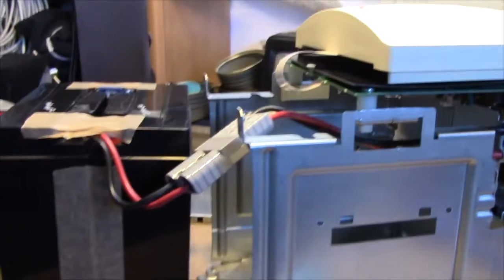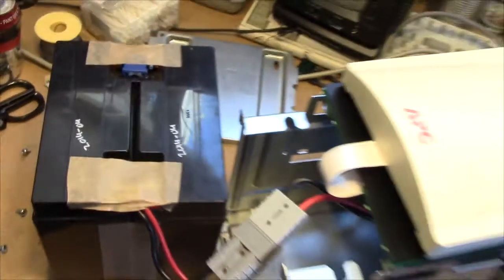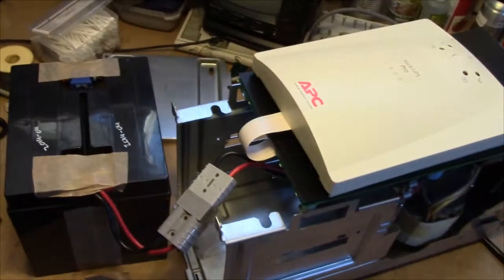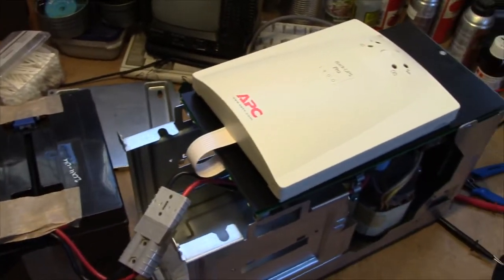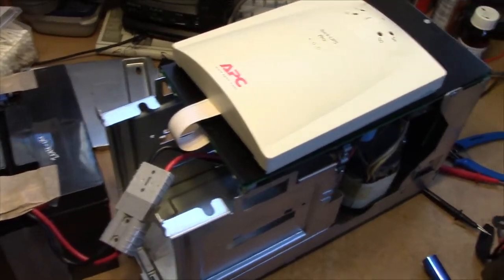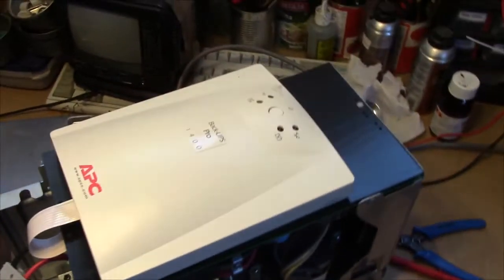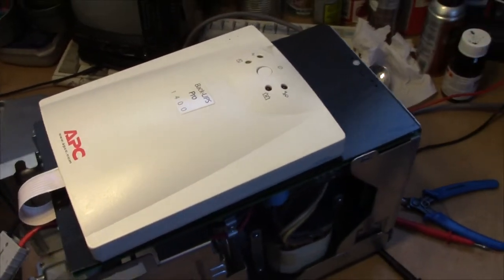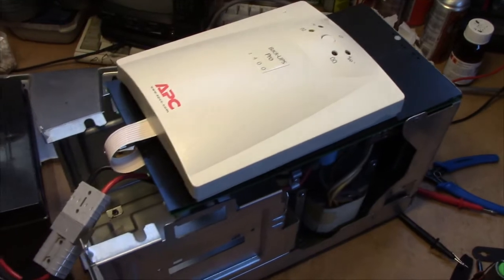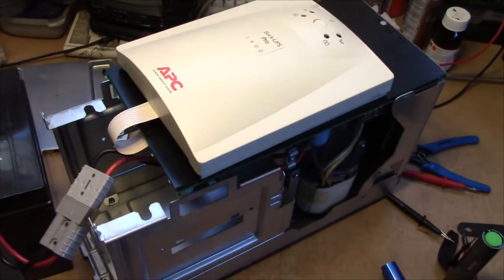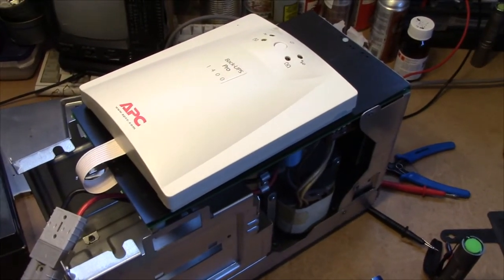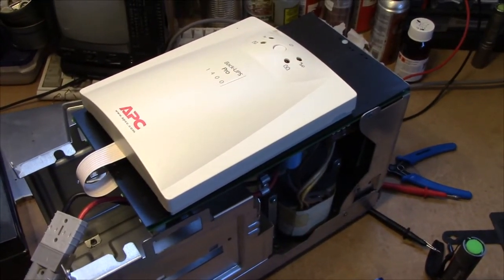So this thing was very groany when I started up on battery for a test before I replaced the caps. So let's see if that problem's gone away.